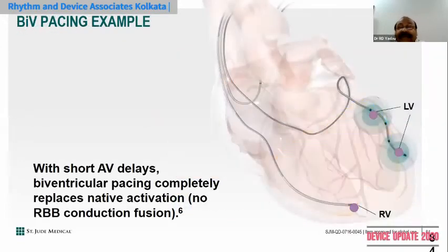So like this, with a short AV delay, biventricular pacing completely replaces native activation. So no RBB conduction fusion here.